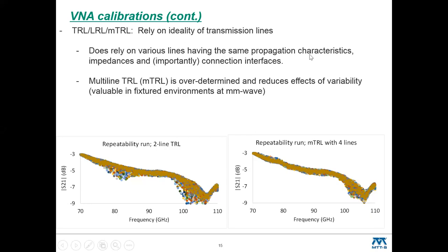That's where this method can run into a little bit of trouble. If you have a low repeatability environment, the launching parasitics aren't consistent, and in that case the TRL family has some problems. But in more controlled environments, it probably has the lowest uncertainties of most of the calibration methods.